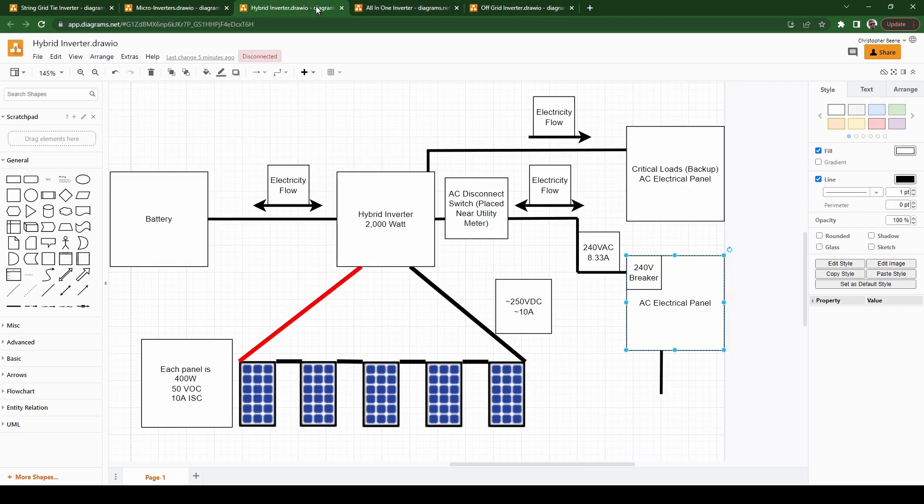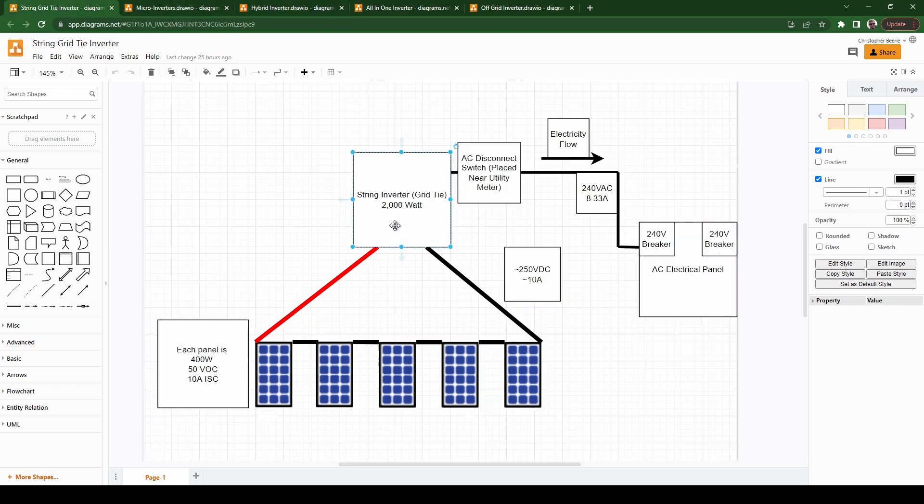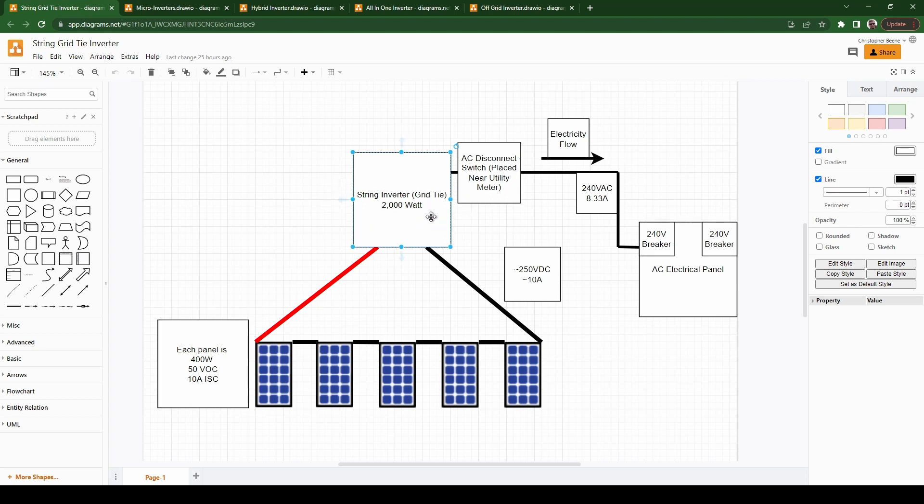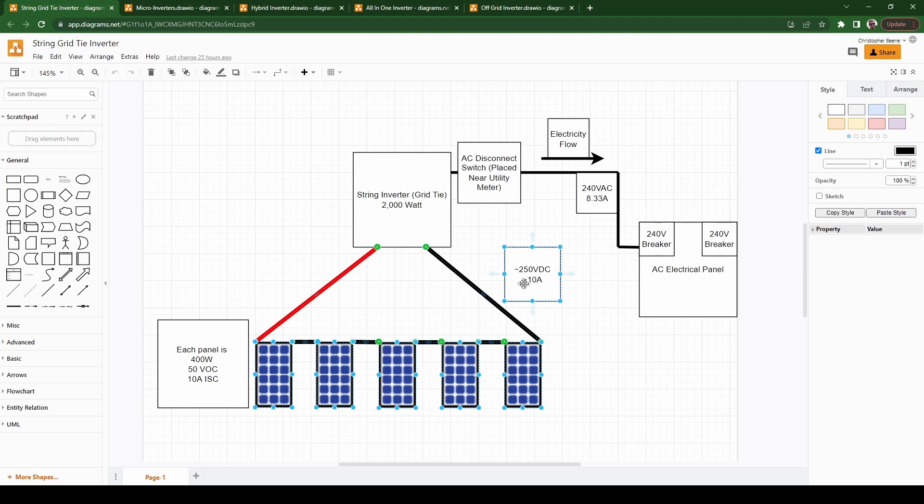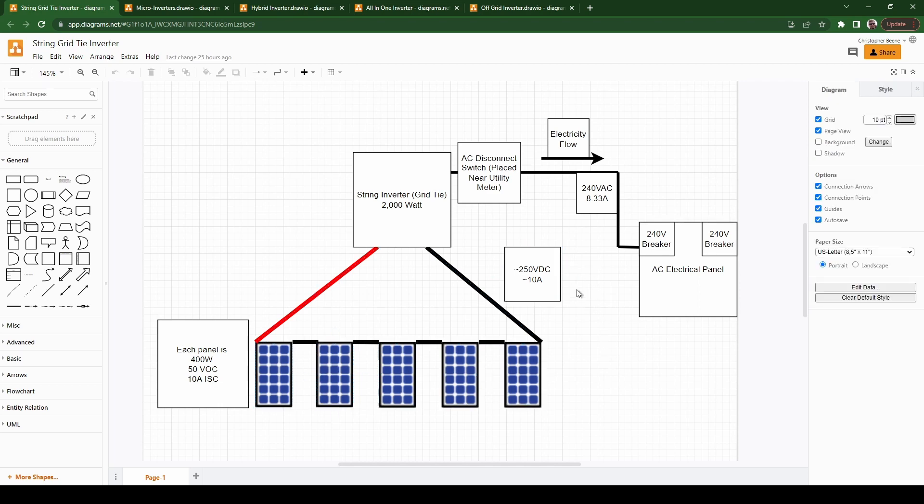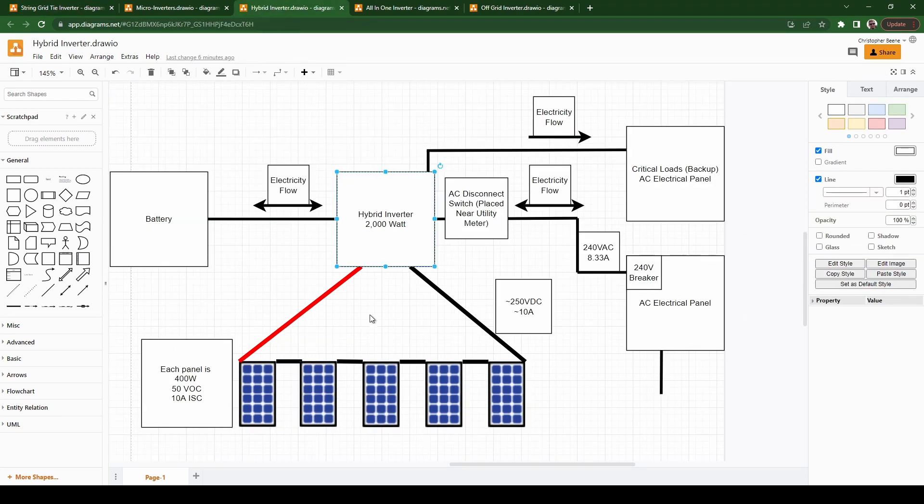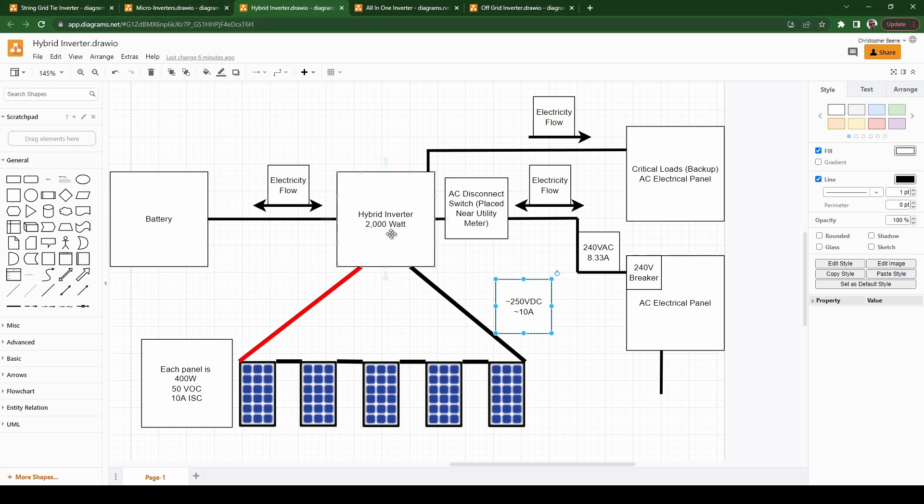In my scenario I really wanted to do a hybrid inverter even when I first put in my string grid tie inverter, but I didn't have the resources to go buy a bunch of batteries. I was like I'm just going to get grid tie in and I can always change later, and I was able to. I installed an array at about 250 to maybe 300 volts. I have five and six panels in series which is a fairly low voltage. I'm able now to buy a hybrid inverter that can support the same voltages and current of panels. I'll be able to just rip out my old string inverter and plop in a hybrid inverter and use the same panels in the same configuration. What I get then is the ability to drop a battery in there and to have a critical loads panel.